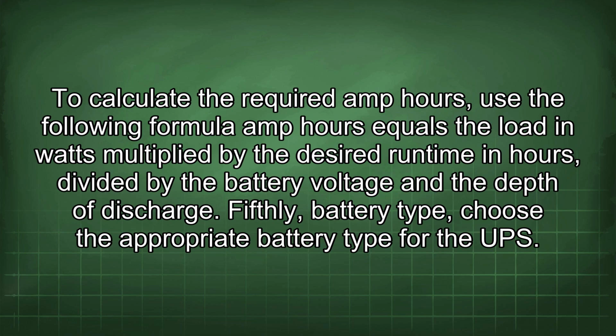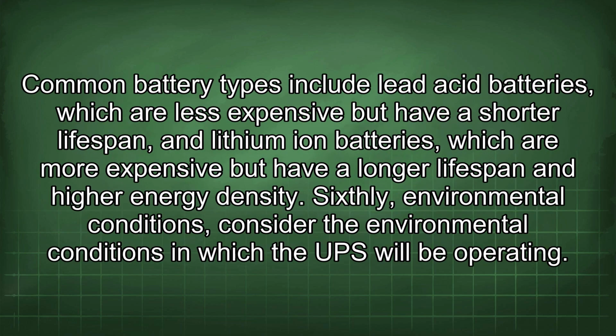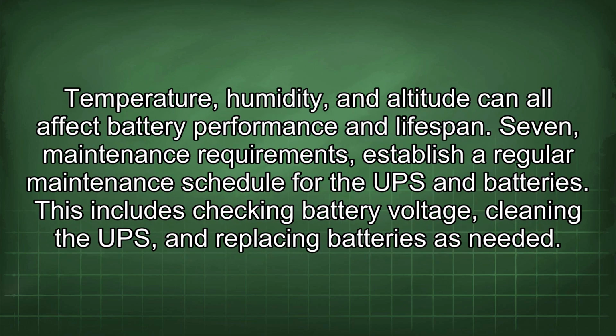Fifthly, battery type. Choose the appropriate battery type for the UPS. Common battery types include lead-acid batteries, which are less expensive but have a shorter lifespan, and lithium-ion batteries, which are more expensive but have a longer lifespan and higher energy density. Sixthly, environmental conditions. Consider the environmental conditions in which the UPS will be operating. Temperature, humidity, and altitude can all affect battery performance and lifespan.